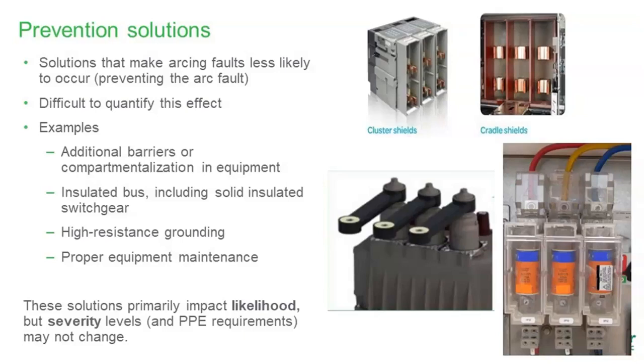Just other equipment construction. On the right hand side was a picture I took in a VFD cabinet that a customer had built up, with some encapsulation of incoming conductors and barriers around the individual fuses. The idea being that this was kind of like our zone 1 that I showed you in the panel board a while ago. You put some barriers around that zone 1, and then anything downstream of that, you've got some added protection.